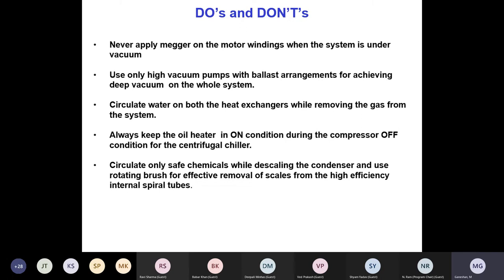Always circulate water on both heat exchangers if it is a chiller when removing the gas. Otherwise the tubes can freeze and lead to tube failure. We have seen this in many places, and we can avoid it. If water gets inside the system, it is like a cancer. Once water is inside, it is very difficult to remove. I think all the senior veterans and service engineers will tell you how difficult it is to remove the moisture from the system; sometimes it takes even one month to remove it from the entire system. Always keep the oil heater in the on condition if it is designed that way.